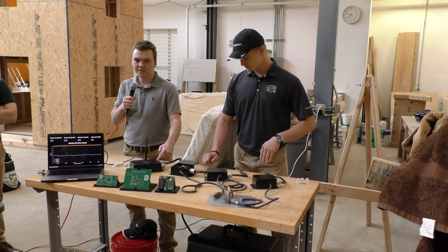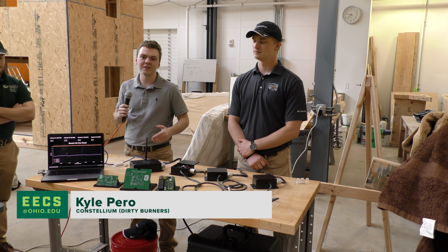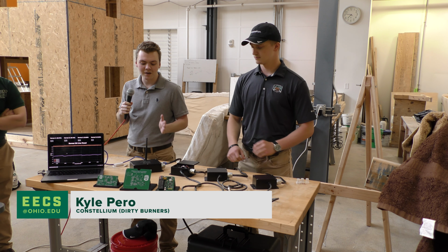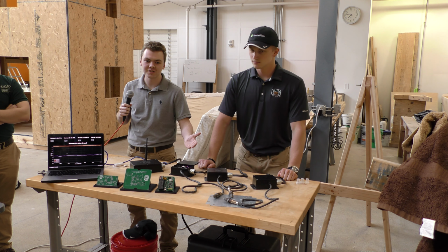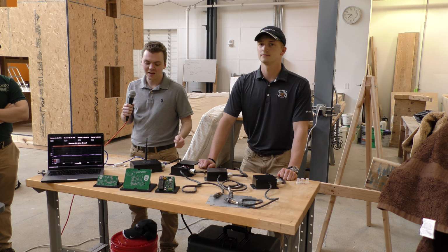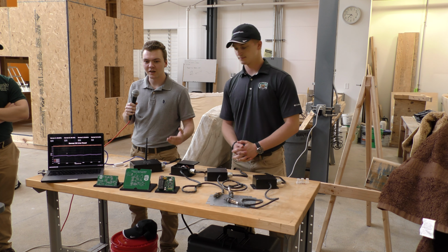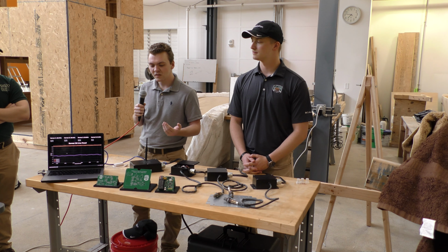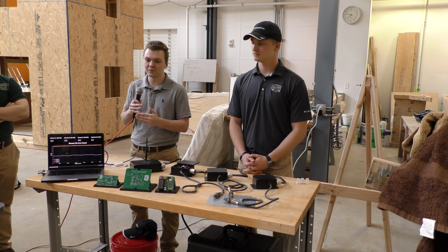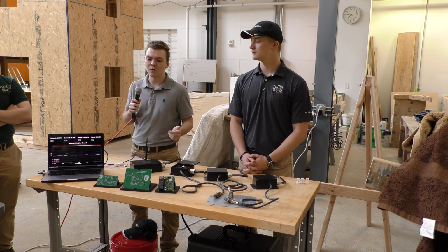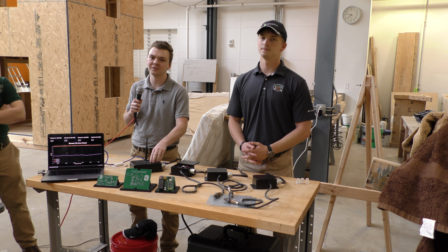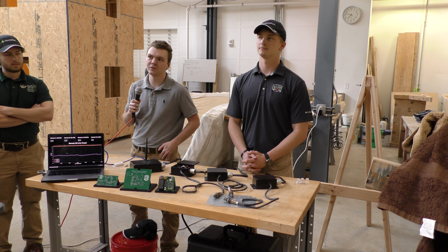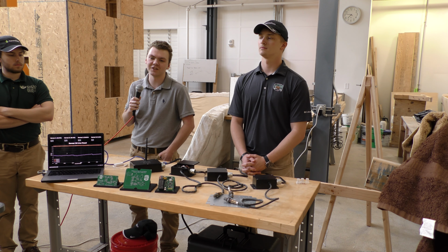Okay, so here's the Ethernet panel. This acts as the brain of the entire system here. It will ping each monitoring panel to request the current data, and after it receives that data, it will be transmitted through Ethernet to the plant network. This can be used to have an overall trend line of all the data, while also storing locally on the Ethernet panel for further observation later on.